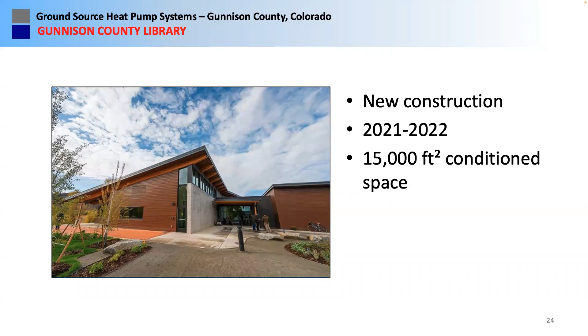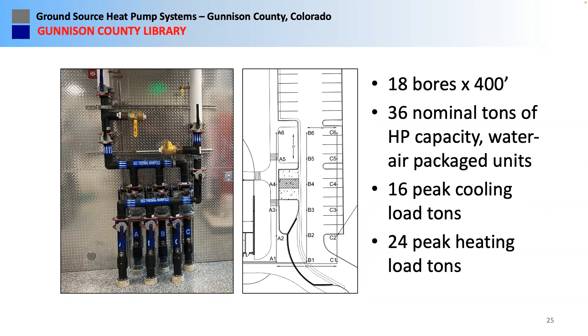So we got into a little bit easier geology. In fact, we have some high thermal conductivity values. When we got the thermal conductivity test back, I was pretty amazed. We got 36 nominal tons of heat pump capacity, all distributed water-to-air heat pumps, with 16 peak cooling load tons and 24 peak heating load tons. And this is a decoupled ground loop, by the way. So the ground loop does not work unless it needs to temper the interior building water temperature. Next slide, please.